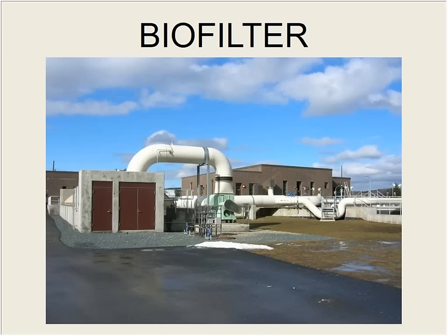the big tanks filled with a media. Could be wood chips. They actually have a foundation of lava rocks. Remember back in the 80s, you get a grill, you had those funky little lava rocks. Loaded with that and then a bunch of wood chips. And organisms actually live on that media and will consume the odorants as it goes through. So you walk at the end of this where it discharges, you don't smell a thing. That's a very, very good job.